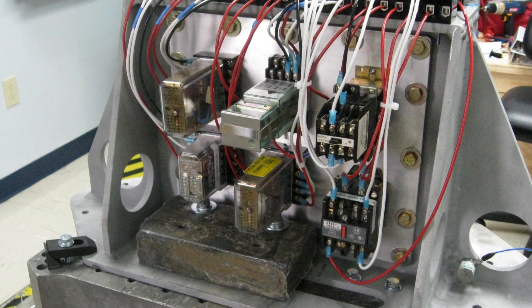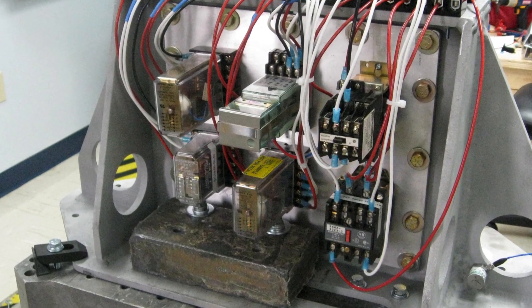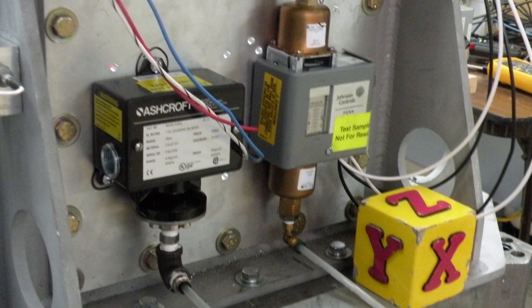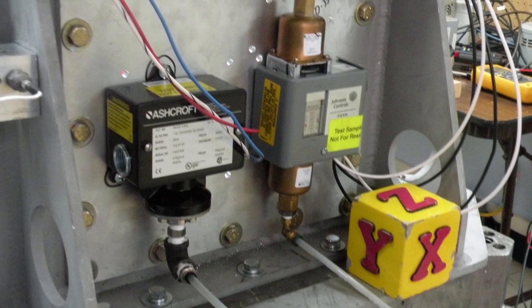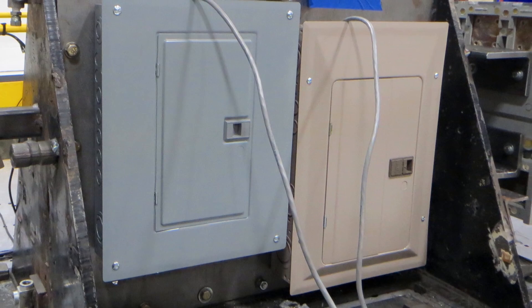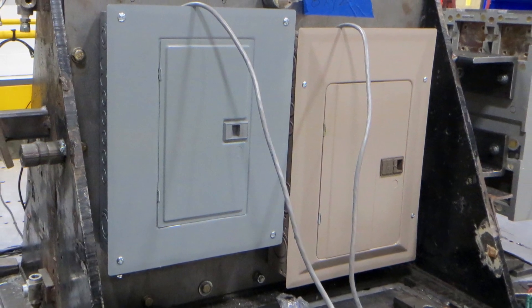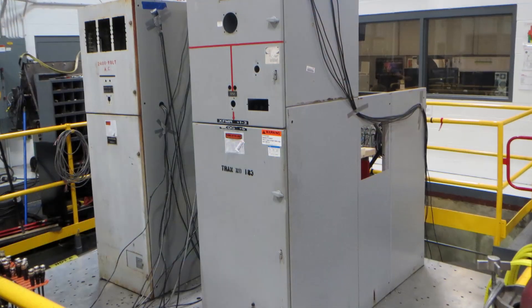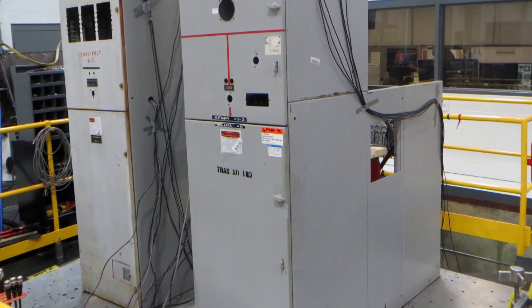This chart shows the distribution of the kinds of parts we are testing in this program. The entire high-frequency program will test about 150 parts. Many of them are relays that are used to control systems in the plant. Others are pressure sensing devices used to monitor fluid pressures throughout the plant and provide information to the control systems. And still others are circuit breakers — some similar to breakers you would find in your own house, while others are very large breakers called switchgear, which operate at 4,000 volts.